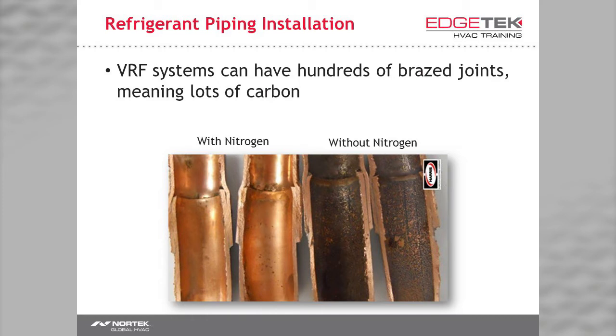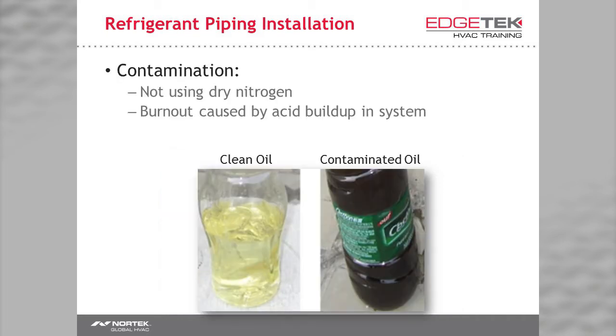On the left is how the inside of my piping looks after brazing. On the right is my sales manager's piping after brazing. I'm kidding, of course. The black substance is carbon, right? PVE oil, or the type of oil we use in all of our VRF and mini split products, is a pretty decent copper cleaner. It'll take all of that black stuff in your piping and take it back to your compressor. Over time, this can cause excessive wear and tear on the internal components, contribute to oil breakdown, and spray black oil all over your brand new Nortek shirt when you disconnect your hoses.